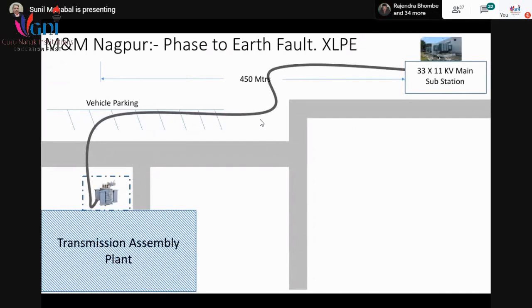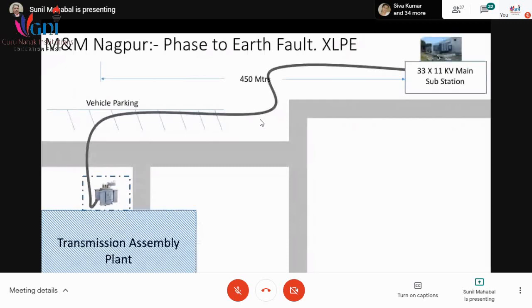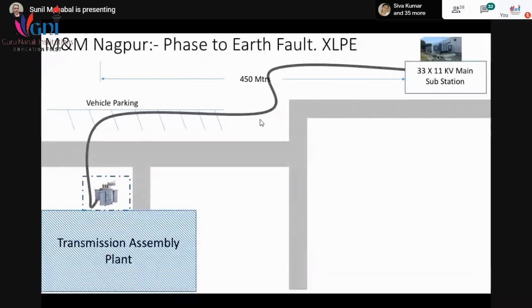Then we connected this, which was laid around 2 years ago. Okay. And as soon as we charged it with 11 kV, the circuit immediately tripped and it tripped everything. There was a dead short circuit somewhere. And now, somewhere in 450 meters, how to find out where it has shorted and what the fault is?